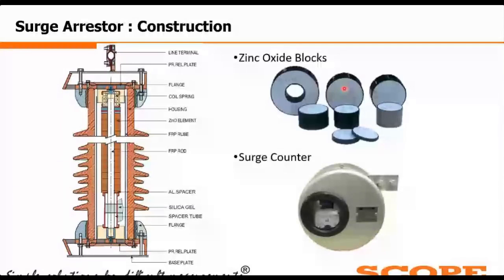And then at the bottom, from the base plate, the direct earthing strip will be going to the earthing. While going to the earthing, we can see this surge counter. This is the surge counter. Along with that, there will be one leakage current meter commonly installed in all the LAs.